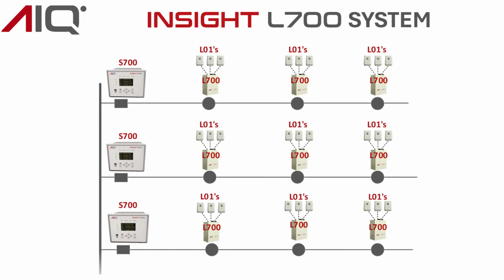In order to understand the L700, we will first look at the overall architecture of the system. The L700 consists of a network of substation installed sensitive earth fault and voltage measuring devices called S700s with distributed line mounted sensors. The line sensors communicate to their local data concentrator via short range radio, delivering fault and disturbance current activity, including sequence values of current. All data measured in the substation or at the distributed nodes is time synchronized to the GPS clock to within 1 microsecond, making the entire system data time coherent.